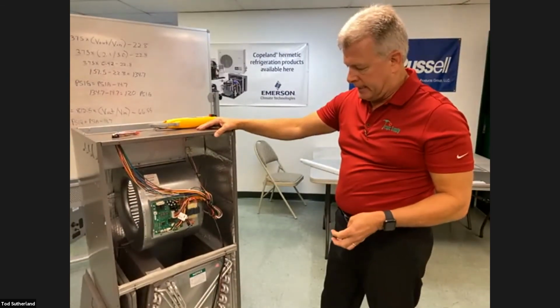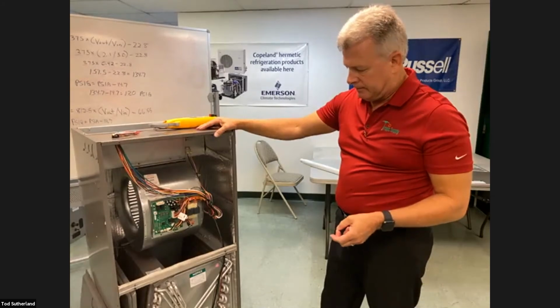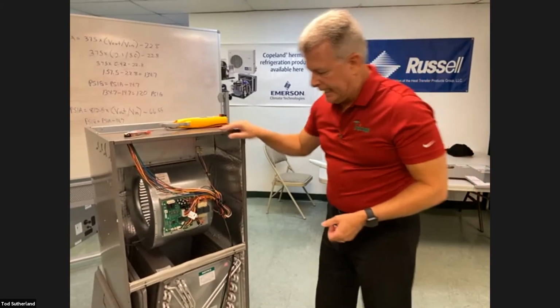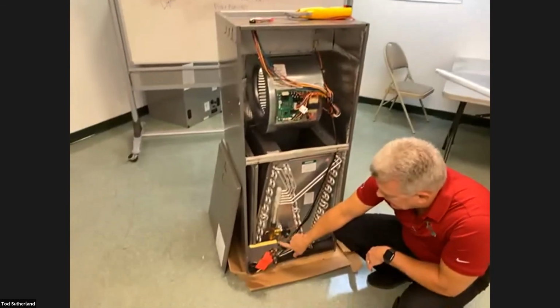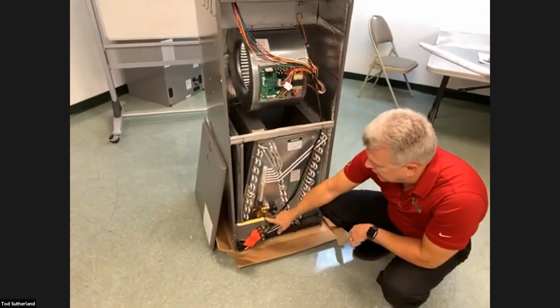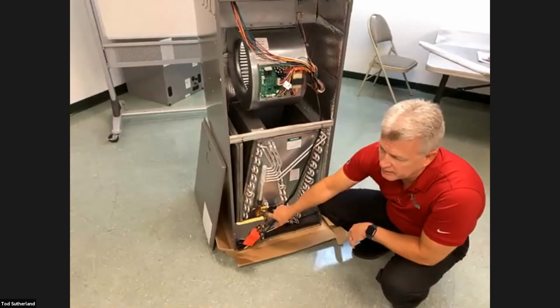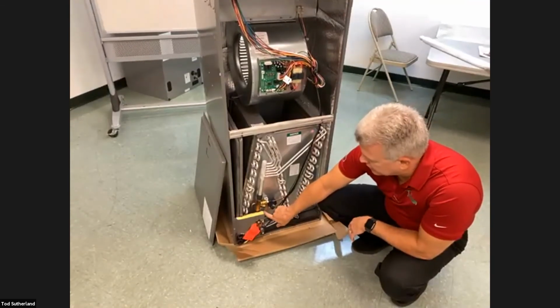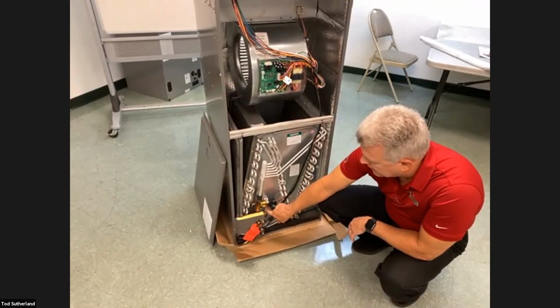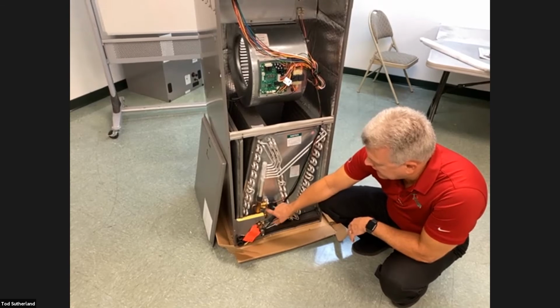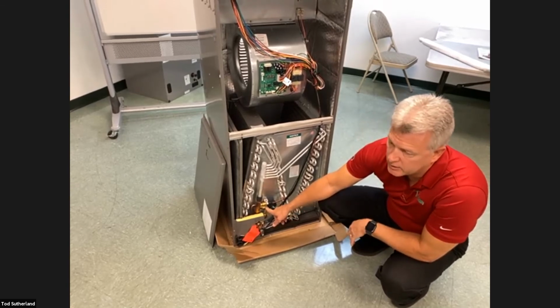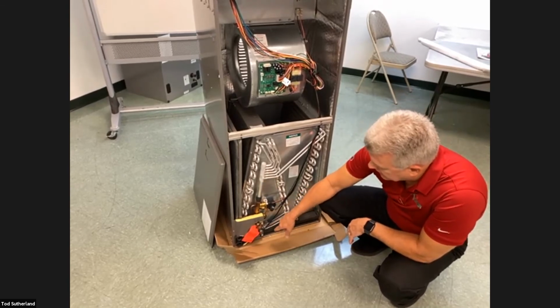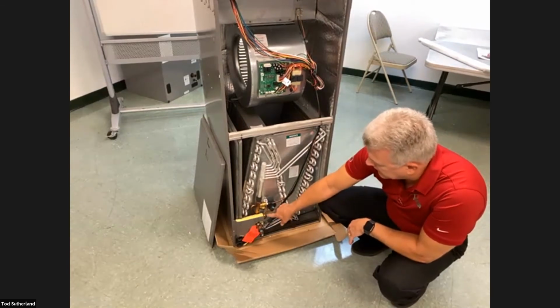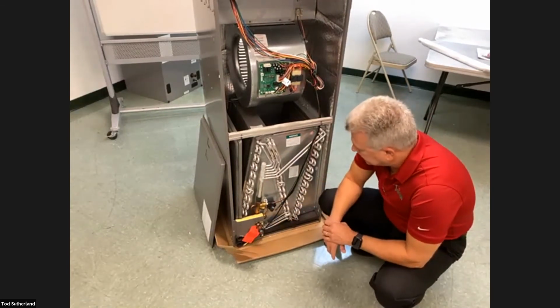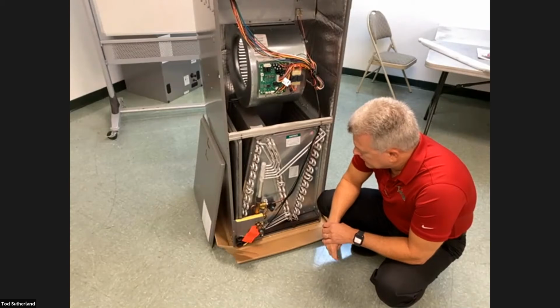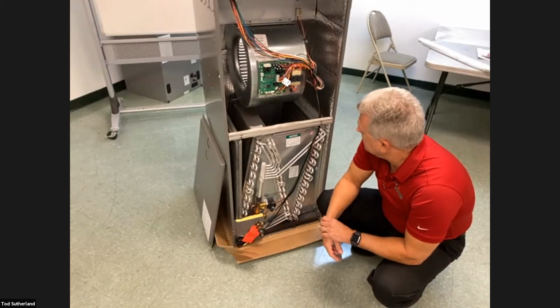Trying to think if there's anything else. Again, we talked about on the EEVs, test the EEVs. If we're in heating mode, the indoor EEV, of course, should be bypassed. So you would take a temperature reading of your line coming in and out, okay? And there should be the same temperature reading there. If you want to check it in the cooling mode, you should definitely see a difference between here and here, because now you're metering through here. And I think that's about it.